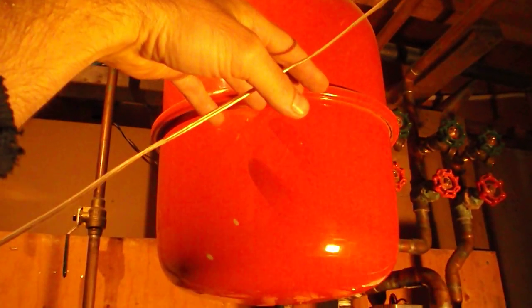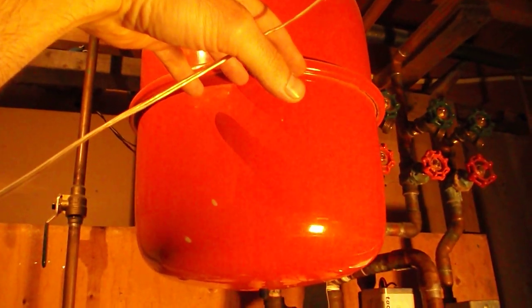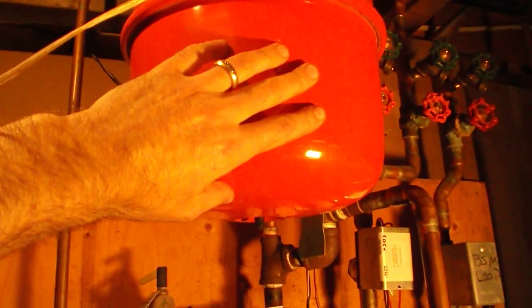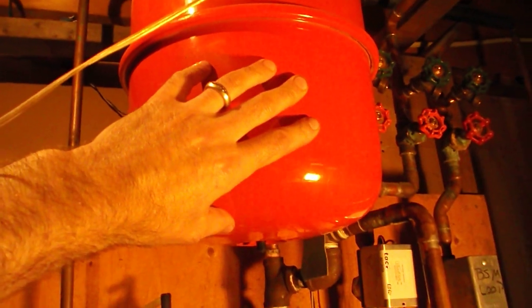And that unit has air pressure in the bottom, and as the temperature of the system heats up and the water expands, that increases the pressure in the system, and water will drop down into this chamber and allow for the air to get compressed without building too much pressure in the zone.